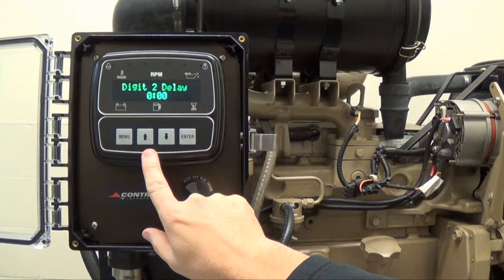A time delay can be associated with the digital input feature and is adjustable between 0 to 60 seconds. In this video, there is currently no time delay programmed for the Digital 2 input. Since none is necessary for the low float action, the operator leaves the delay set to 0 seconds. This way, the pump will start as soon as the fluid levels reach the high and low floats.